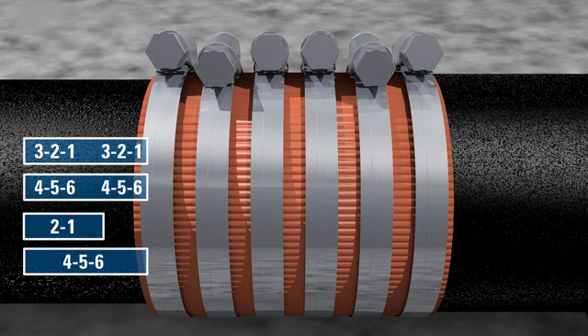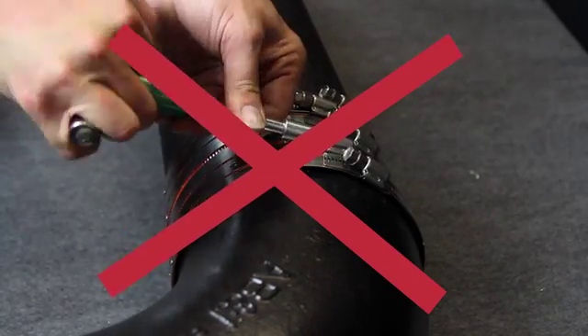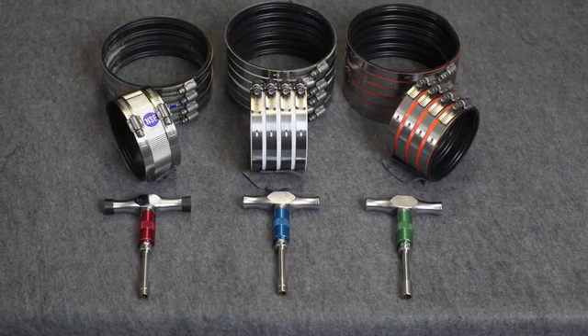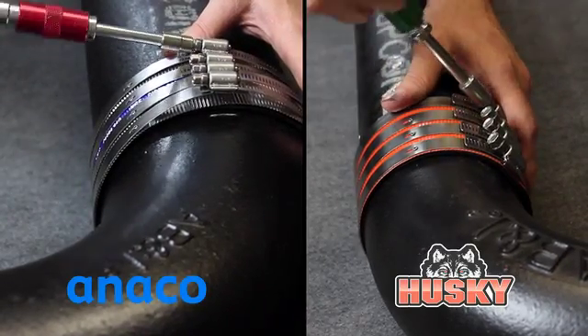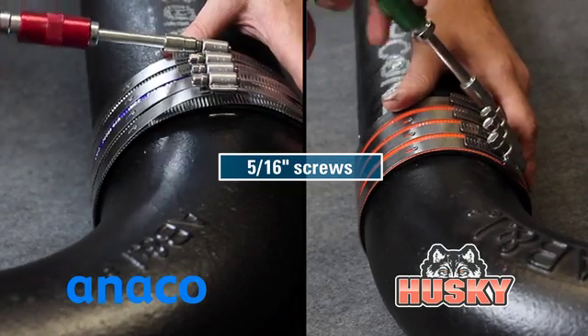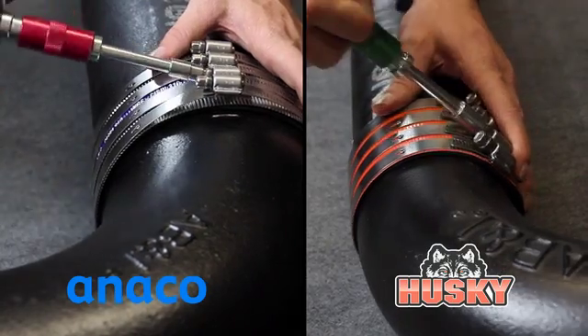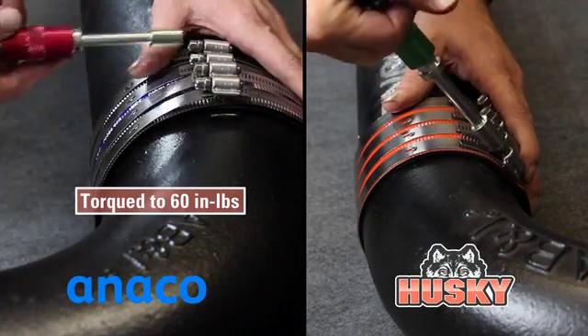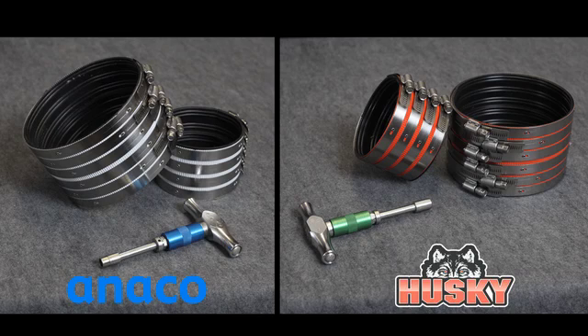Once the couplings are installed and torqued to 80 inch pounds, it is not necessary to go back and re-torque the clamps. Installers should remember to always use the correct torque wrench when installing Anaco or Husky couplings. Both Anaco Standard and Husky 2000 couplings feature a five-sixteenths inch screw, but the same wrench should not be used for both. Anaco Standard couplings are to be torqued to 60 inch pounds, but the Husky specification calls for 80 inch pounds. This has been a source of confusion, so be careful to use the wrench that provides the correct torque for the coupling being installed.